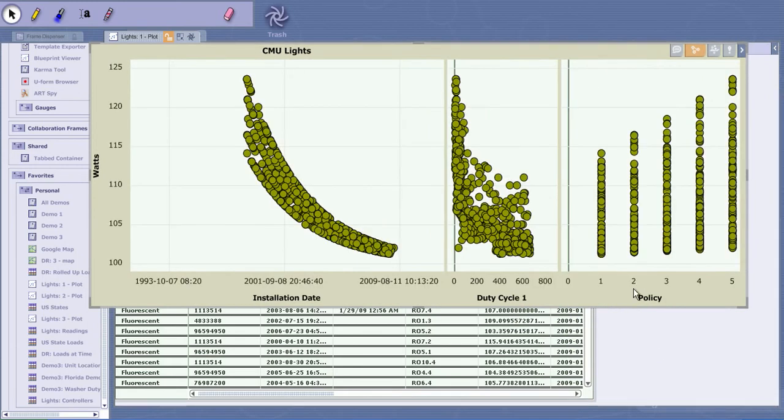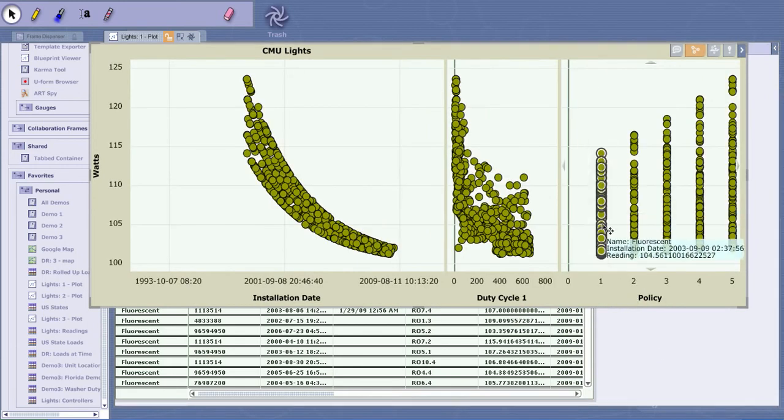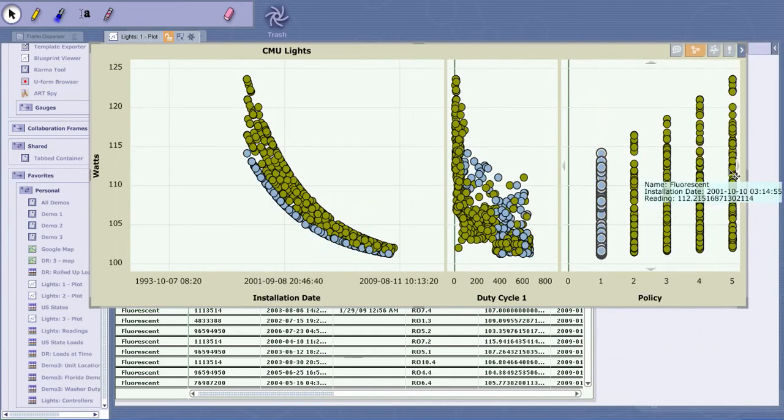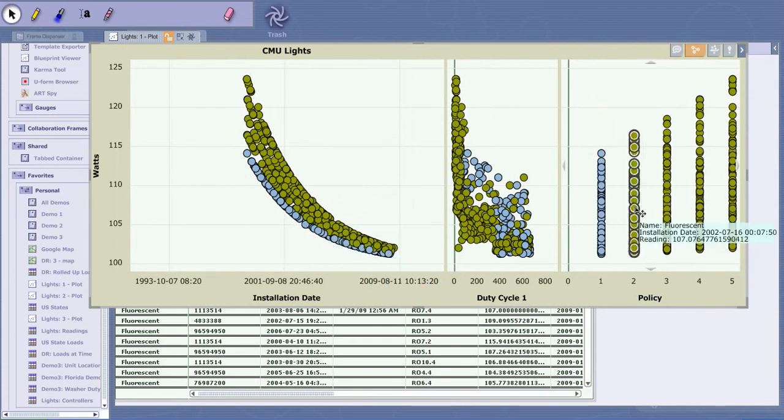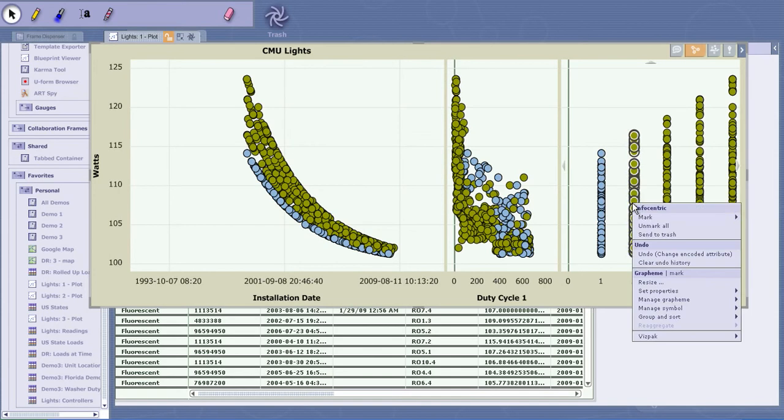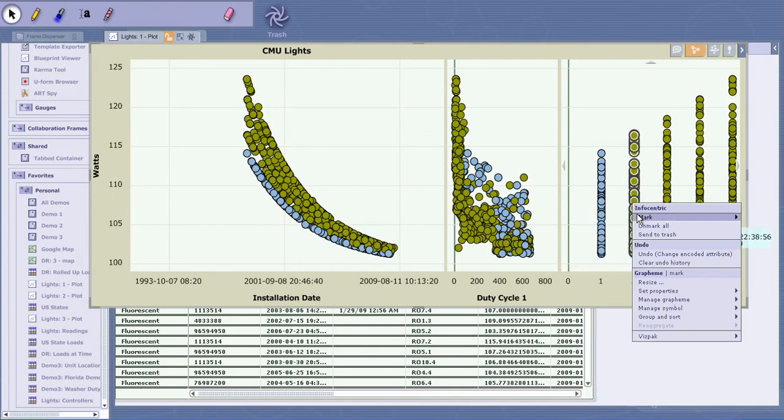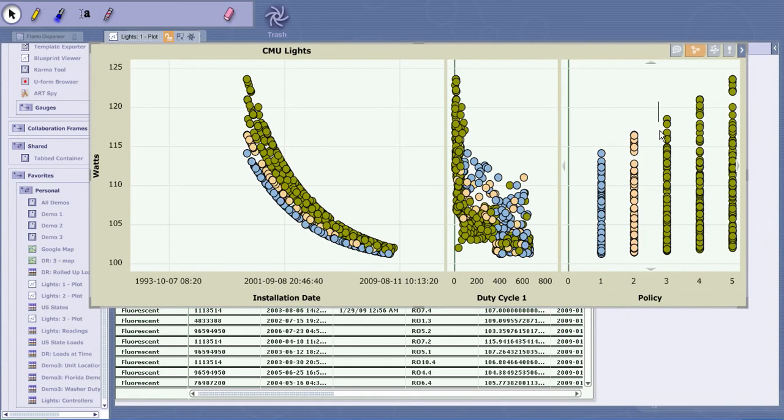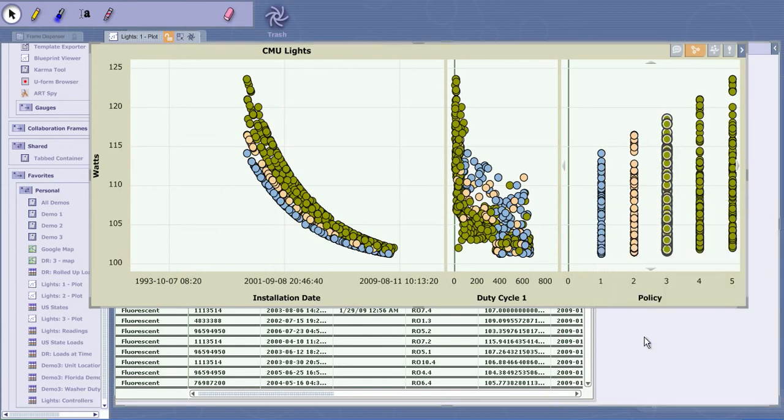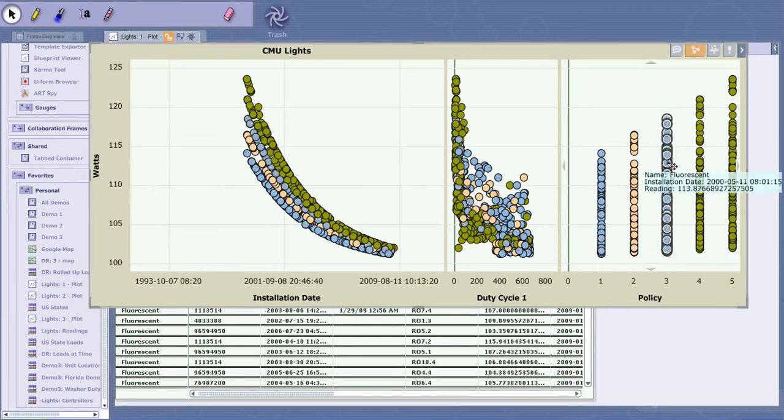Now I can start to see some things from policies of how people have set up these lights. They're smart lights. Duty cycle one shows up directly as that striation - that's like the best policy because it uses the lowest wattage even for stuff installed a while ago. Maybe that's automatically turning things off at the end of the day, or maybe it's a policy that says if this light is really inefficient, turn it off after an hour so it forces people to change it if you don't have a maintenance crew on a regular schedule.